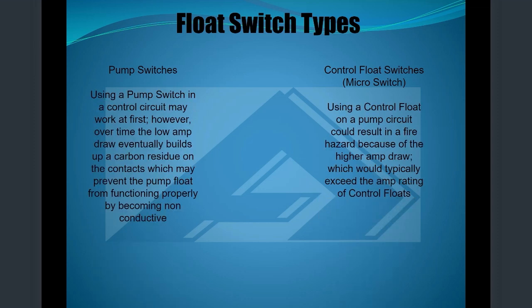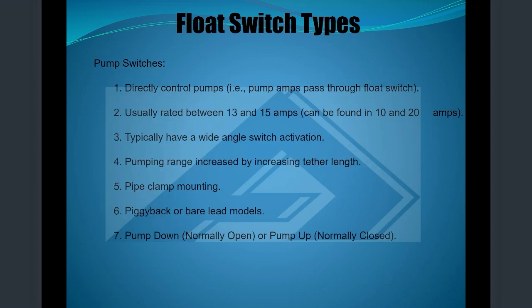Okay, next up. So pump switch, using a pump switch in a control circuit, they work at first. I kind of already covered this. Next one. And so your pump switches directly control the pump, usually rated between 13 and 15 amps. Typically have a wide angle switch activation, which we'll go over real shortly. And your pumping range is increased by your tether length, which we'll also go through. You can have a pipe clamp mounted, or sometimes you could use a cable weight on a pump switch, but typically they're almost always pipe clamp mounted.